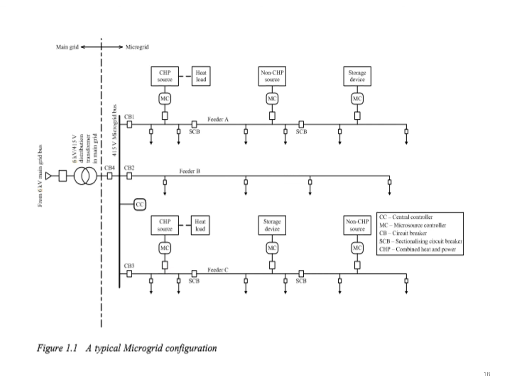In the first option, that is disconnecting the entire microgrid by opening circuit breaker CB4, the microgrid will operate as an autonomous system with all the micro sources feeding all the loads in feeders A, B and C. Whereas if we disconnect circuit breaker CB1 and circuit breaker CB3, what happens? Feeders A and C will supply only the priority loads while feeder B will be left to ride through the disturbance.